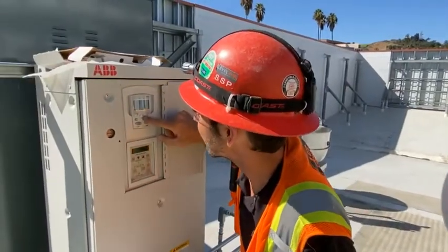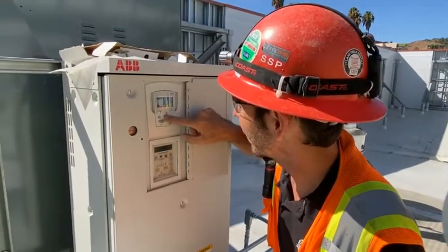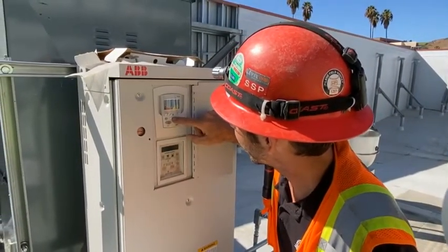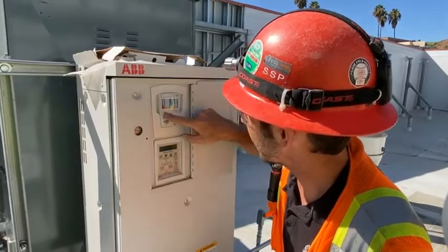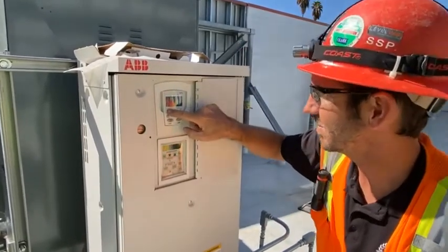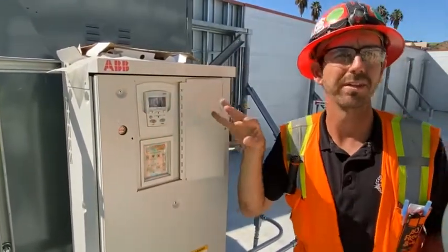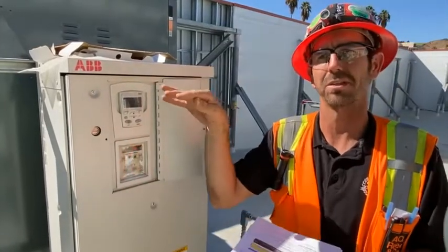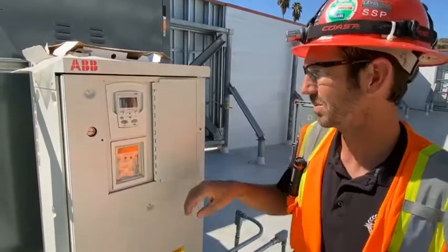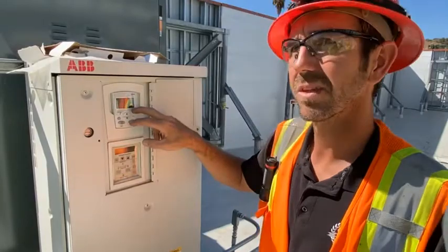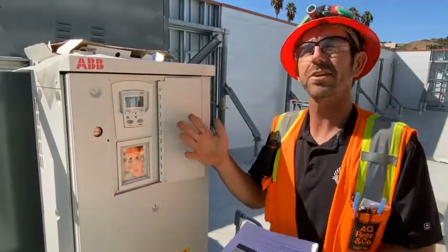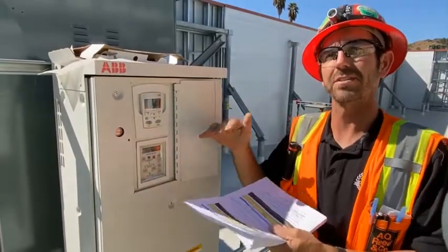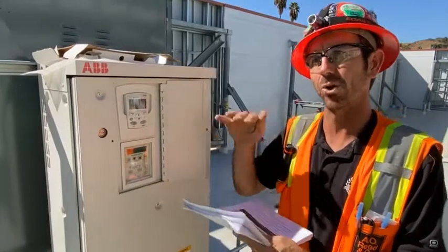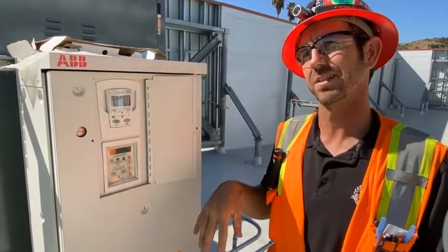So I wanted to just tell you this thing will be running at 43 hertz. 43 hertz is the set point on this fan. So when it turns on, it ramps up to 43 hertz, okay? That's maximum speed, though, right? When it turns on, it goes to 43. 43 is the set point. It doesn't modulate, it only operates at 43 hertz.